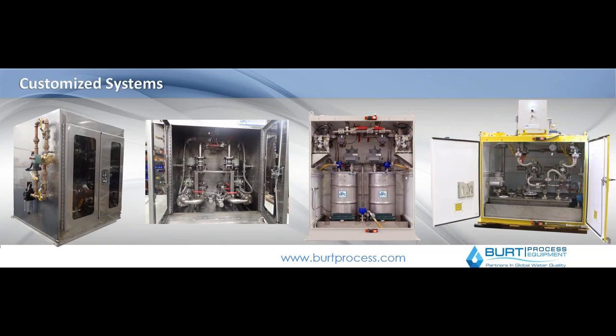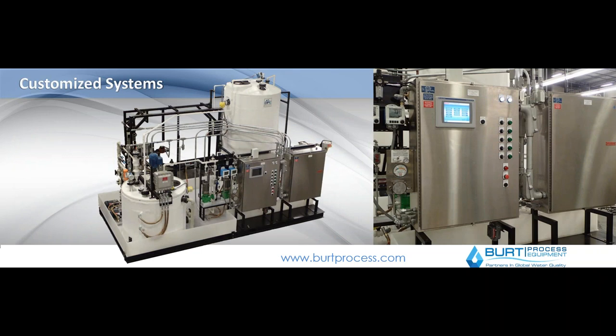This one here is also a hazardous location system for another industrial client — a crop science division. In this system, they're using API 675 metering pumps for HCL injection. You can see the chemical feed system, the storage tanks, the actual mixing tanks involved. This is the chemical injection system, all PVDF, API 675, flow verification, external VFDs located in the purge cabinet. This is going from a very simple chemical feed system into what can be done in the more custom realm for these types of systems.